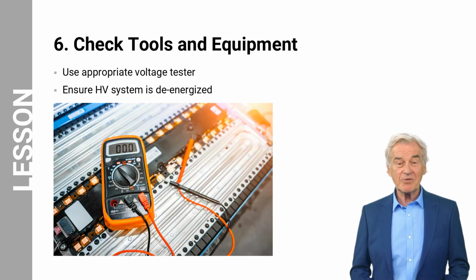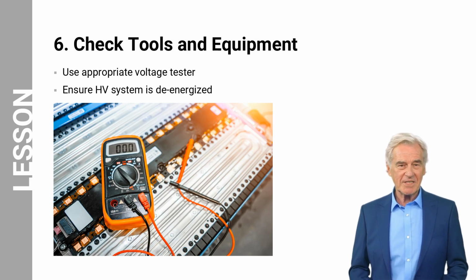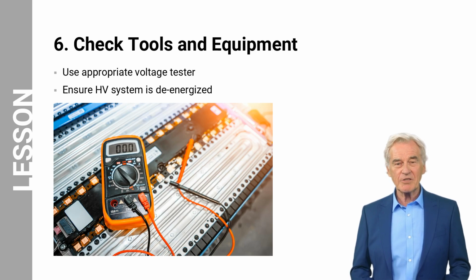Number 6, verify voltage. Voltage verification is a critical safety step to ensure the high-voltage system is de-energized and safe to work on. Choose a voltage tester that is appropriate for the voltage level of the high-voltage system you will be working on. The voltage tester should be rated for the highest voltage you may encounter. Before attempting any work on the high-voltage system, use the voltage tester to confirm that the system is de-energized. This means there should be no electrical potential in the circuits you will be working on. Always follow the manufacturer's guidelines and best practices for voltage testing and ensure the voltage tester is properly maintained and calibrated for accurate readings.